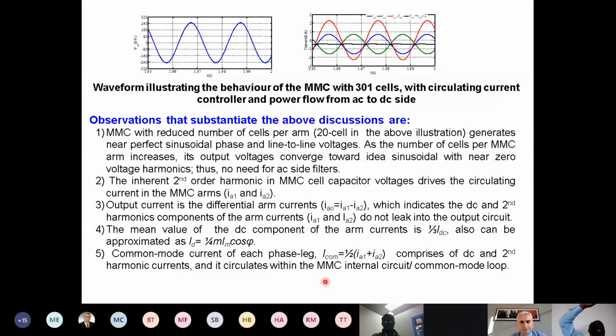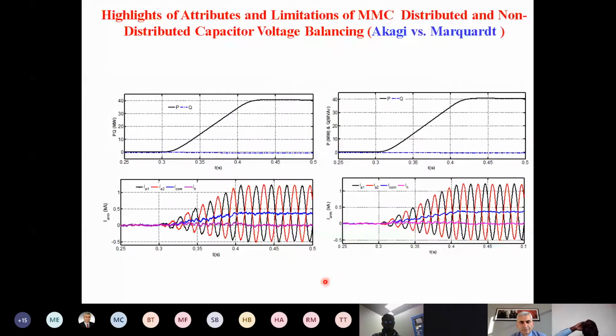And here, this is just a quick look, just to distinguish the two approaches, Akagi against Marquardt, which is distributed based capacitor voltage balancing and sorting based of Marquardt. On this side is Marquardt, and this is Akagi. You can see here the performance, we ramp the power from 0 to 40 megawatt. So the two performances are identical, the arm current identical.